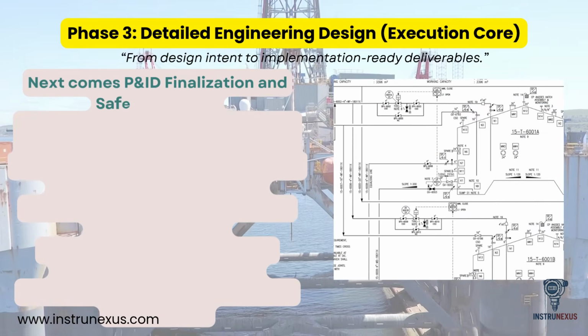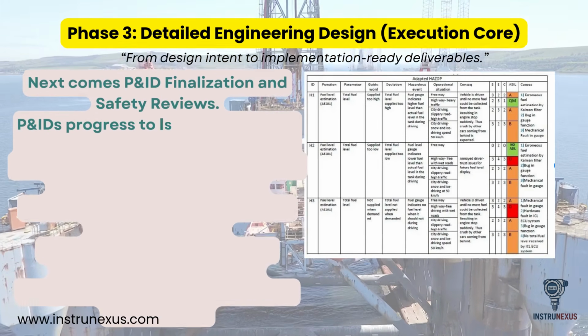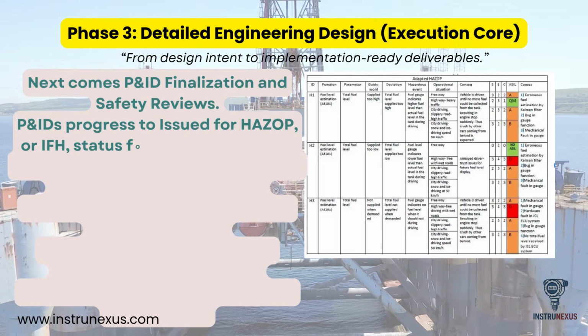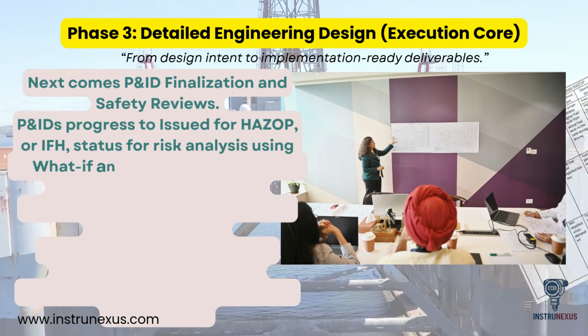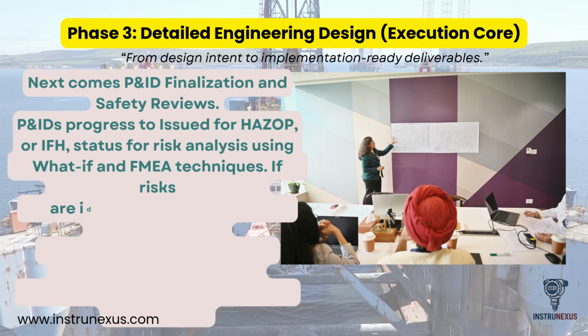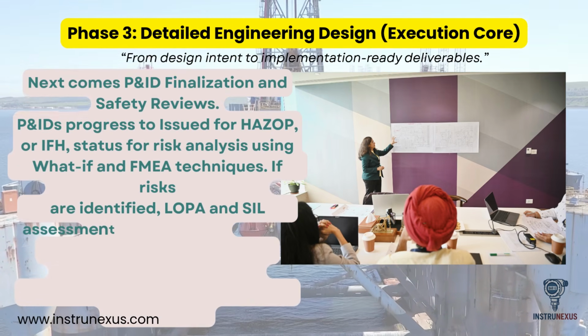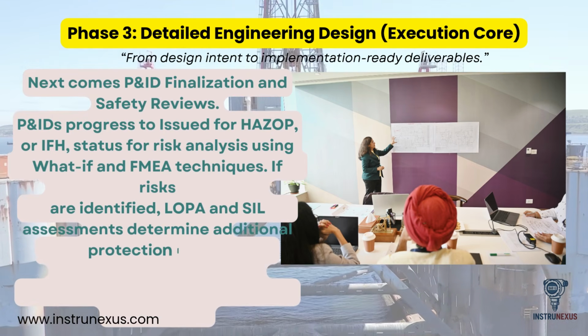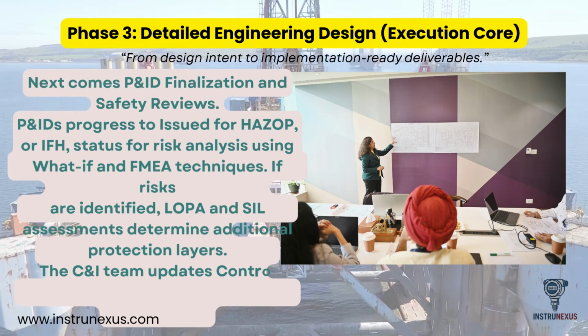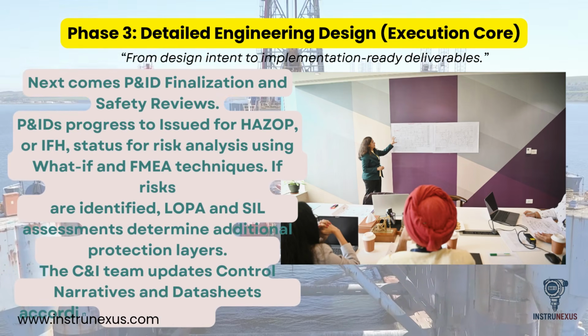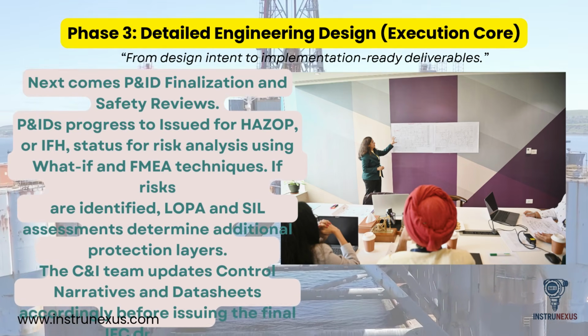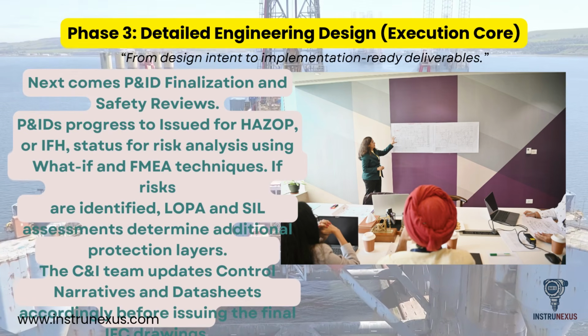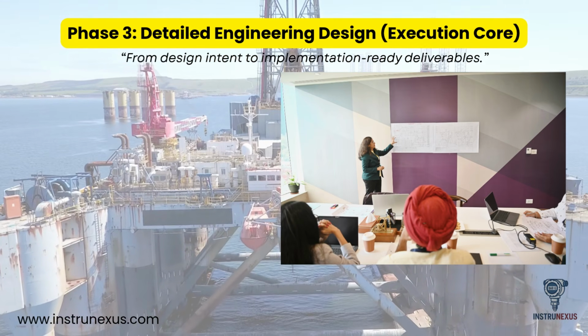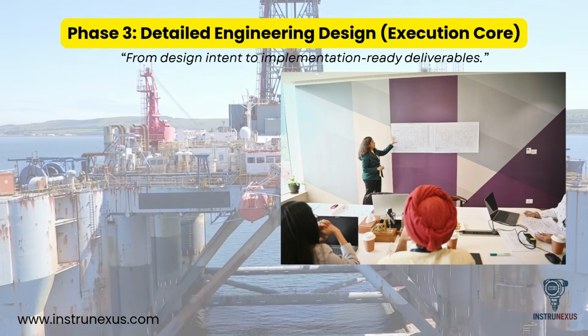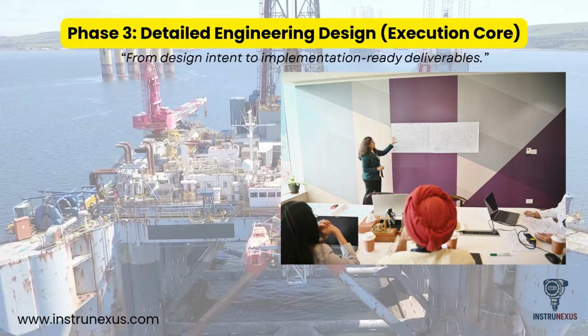Next comes P&ID finalization and safety reviews. P&IDs progress to issued for HAZOP, or IFH, status for risk analysis using what-if and FMEA techniques. If risks are identified, LOPA and SIL assessments determine additional protection layers. The C&I team updates control narratives and datasheets accordingly before issuing the final IFC drawings. Finally, engineers prepare installation and wiring deliverables, including instrument layouts, hookups, loop diagrams, and cable schedules, enabling the construction team to bring the design to life.